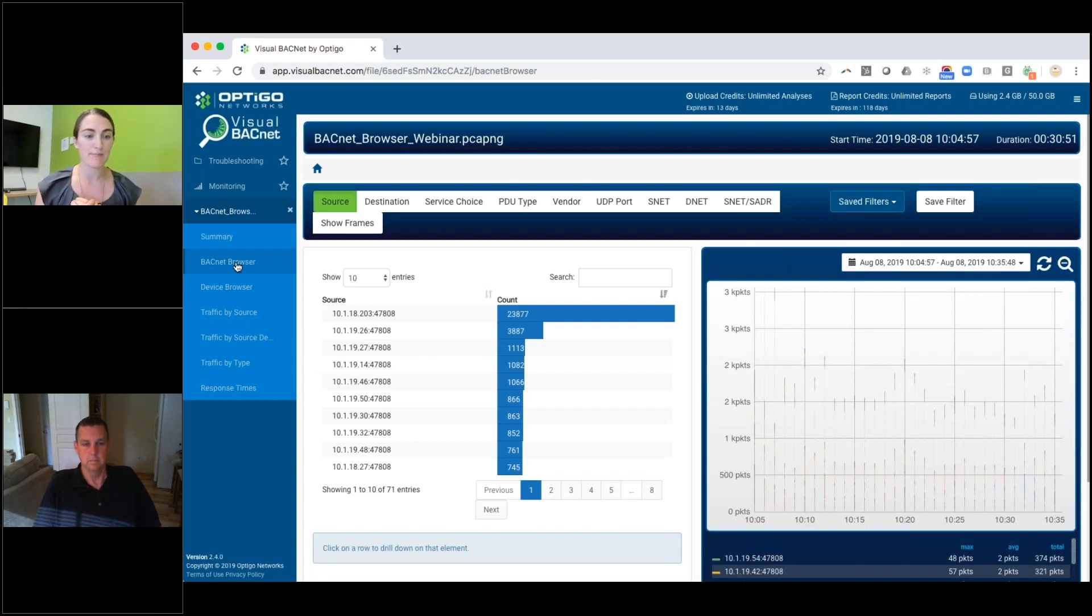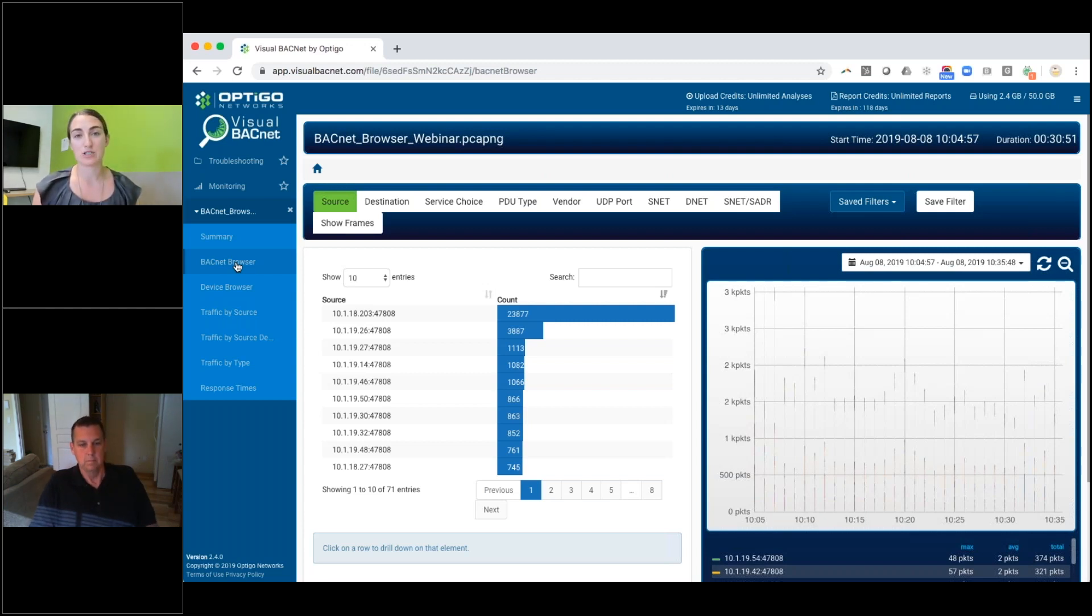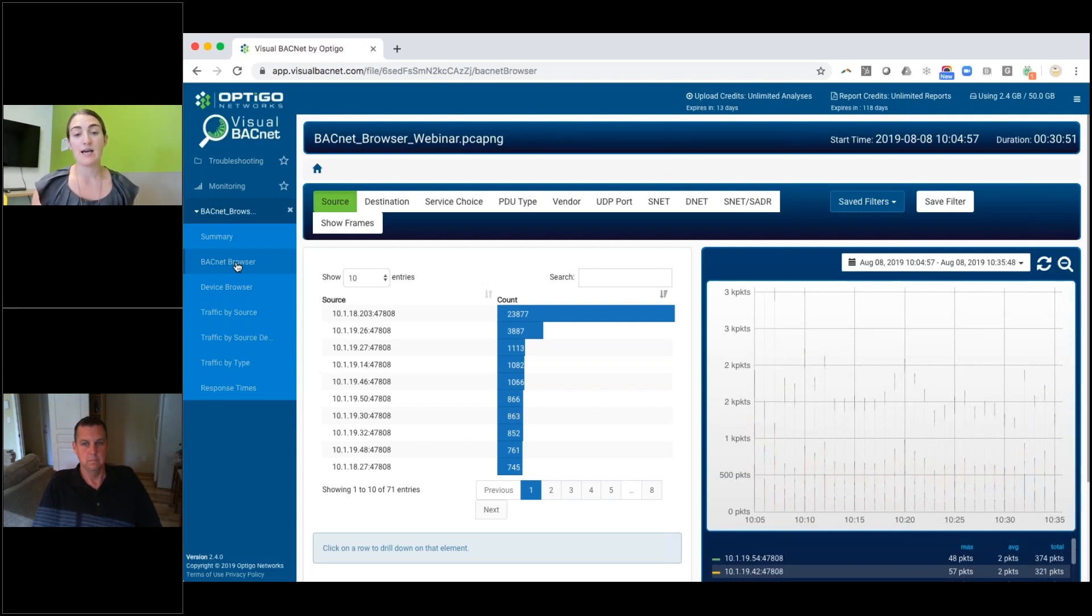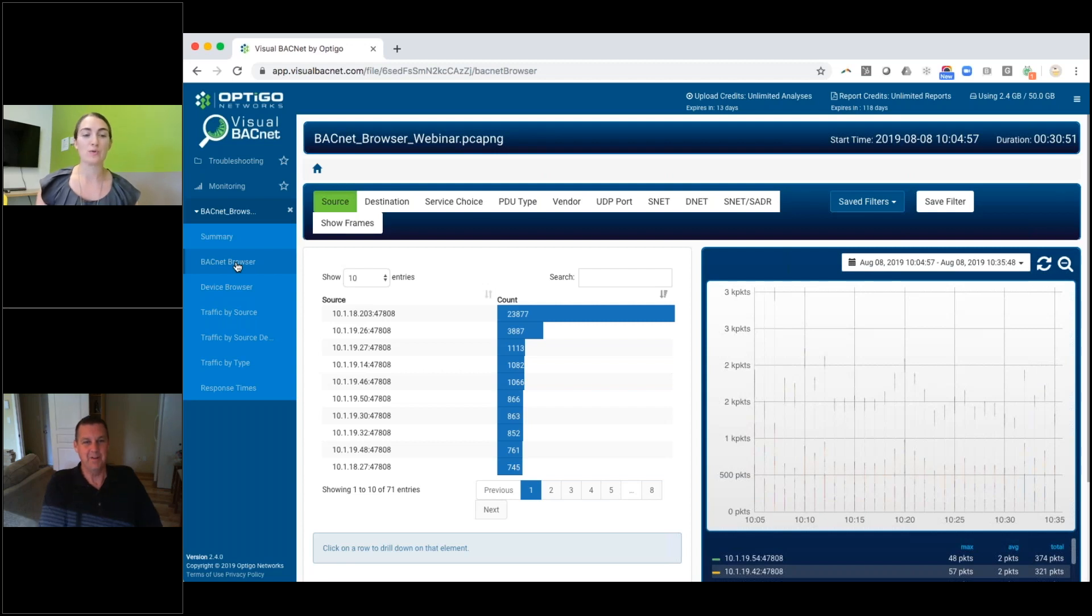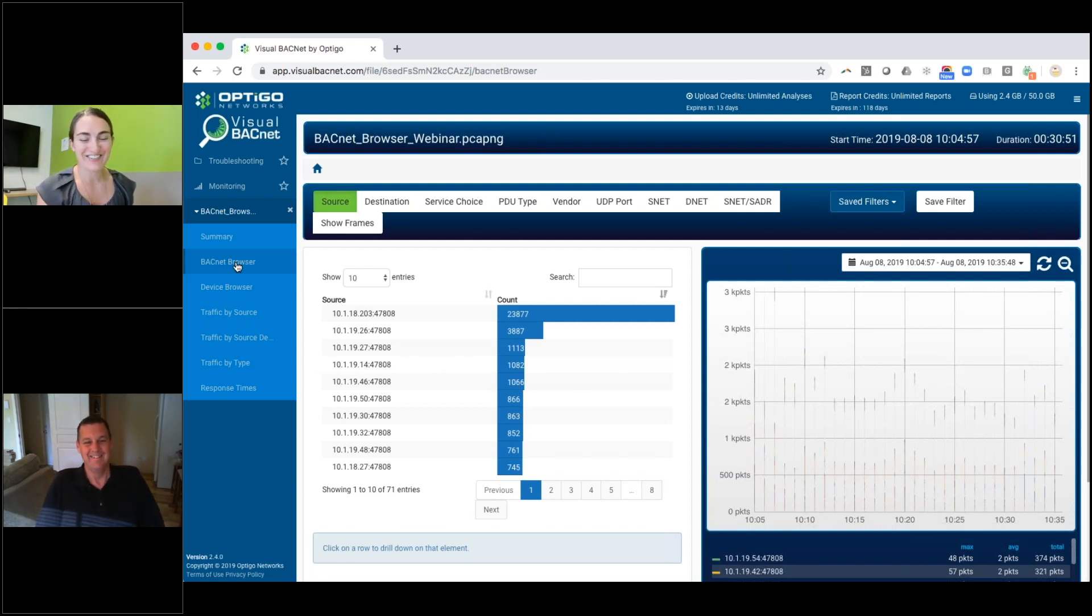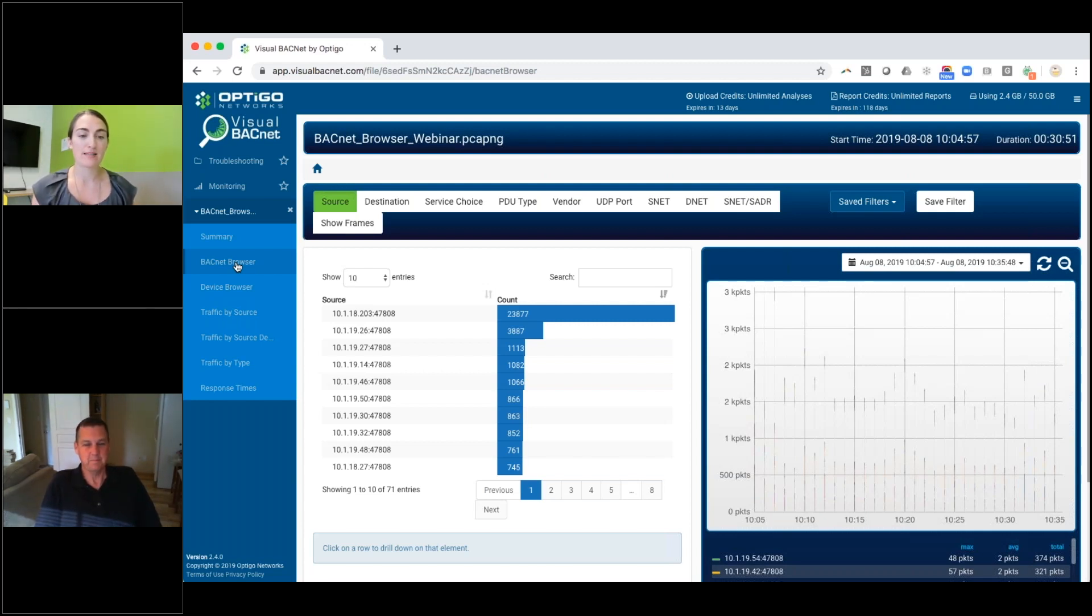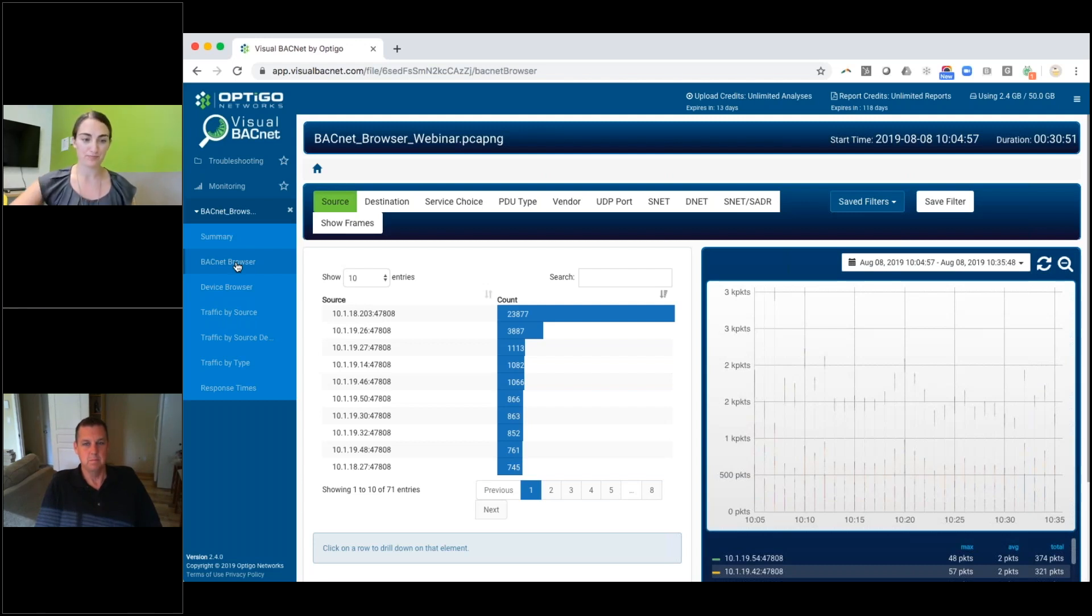So in this example, 18.203 is sending a lot of the packets. It's very likely that that's the server and this is where you need to apply your knowledge. So if that's the server, then that's probably totally fine. However, if that's a little thermostat on the wall, that's not so fine. That's going to be a problem. Your thermostat is sending 23,000 packets. That's a problem. So this kind of applying your knowledge of the site to this view can be really helpful.